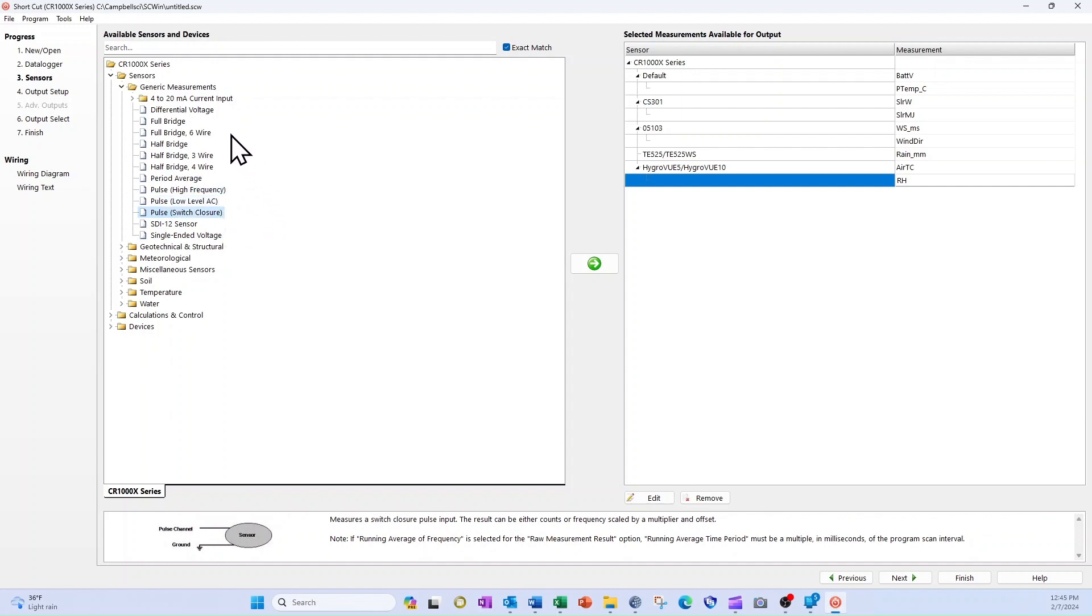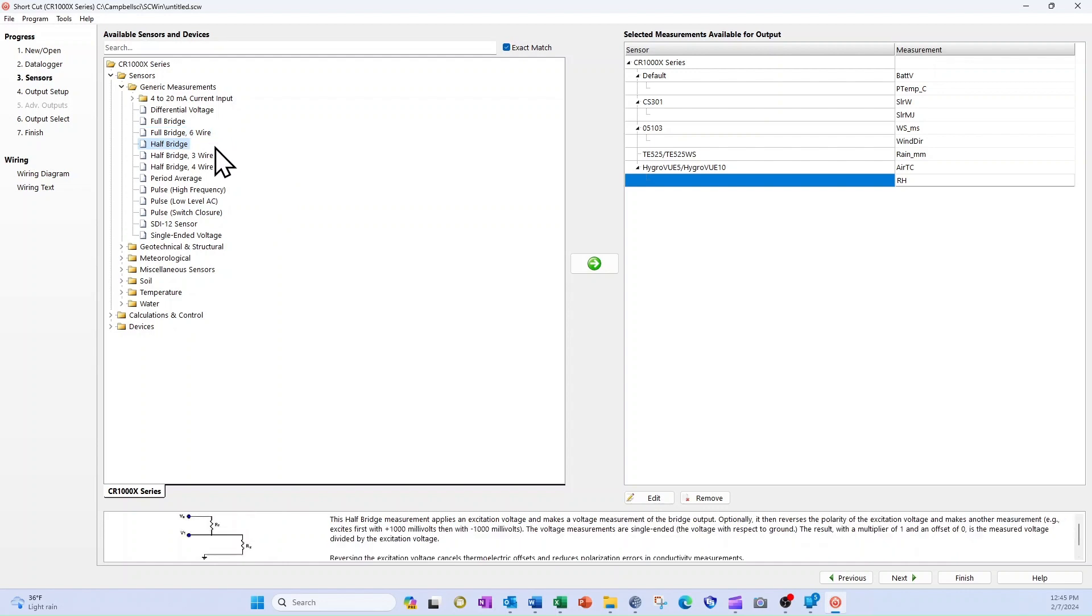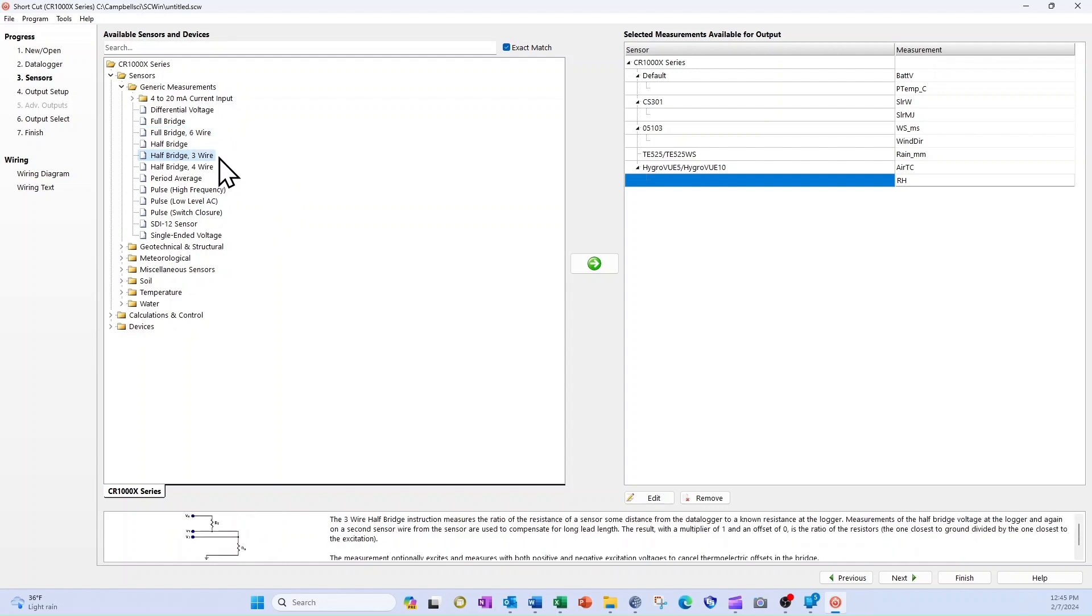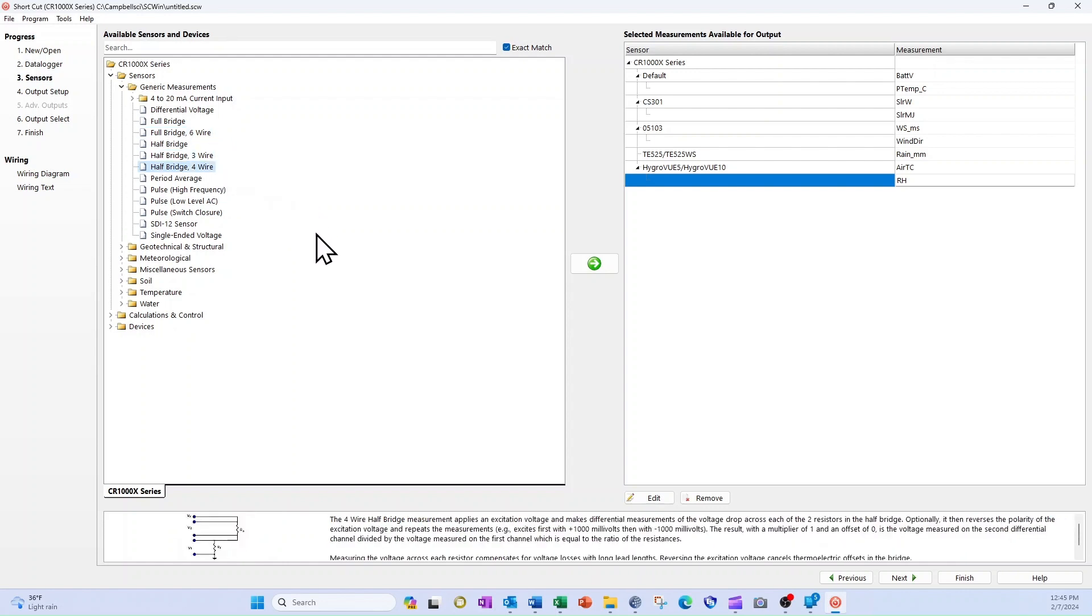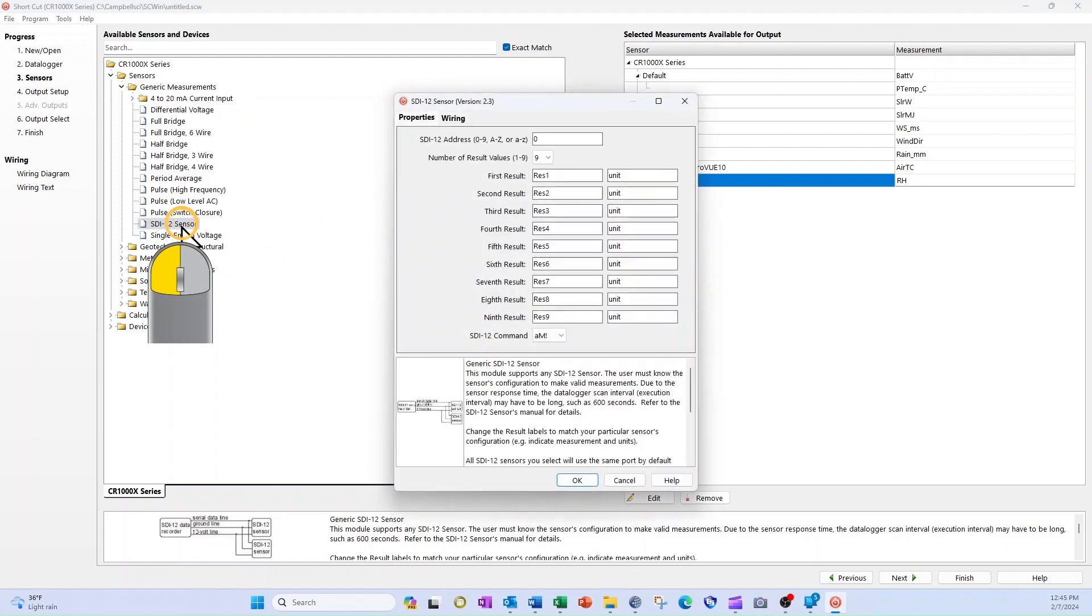Sensors that change resistance with changes to their environment have full-bridge or half-bridge circuitry, so I would select one of these bridge measurement options. In this case, I know the Teros 11 output is SDI 12, so I double-click SDI 12 sensor to open the sensor configuration window.